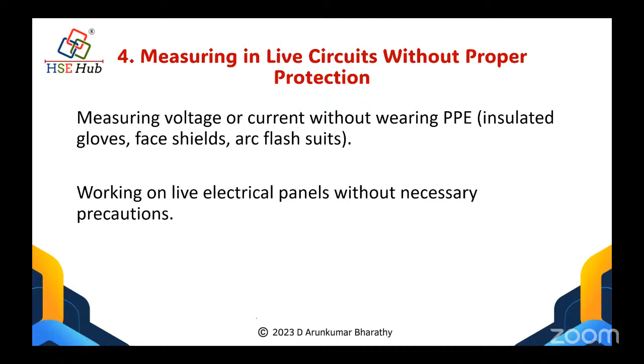In fact, NFPA 70E says the test and measuring instrument is also a part of PPE. Means just like gloves and electrical safety items, the test and measuring equipment is also a part of PPE. So during the test and measurement, there is no option for gloves or shoes. We have to wear all the protective systems. In fact, in some places where we open the electrical panel door and take the measurement, then definitely an arc flash suit or face shield is mandatory. And we will say in another way, whenever we reach the restricted boundary, the arc flash boundary, it is very important to protect ourselves during the measurement also. It is not only for any service or troubleshooting work. During the measurement also, we have to follow the protection system, right?